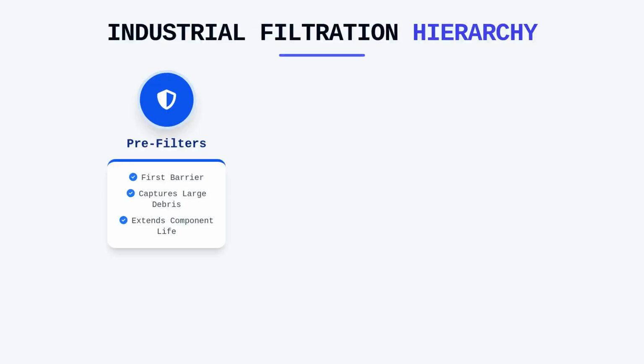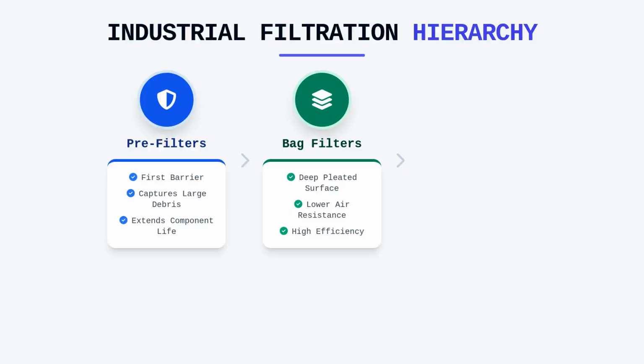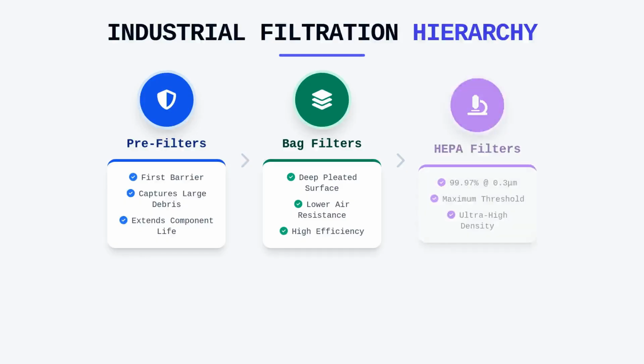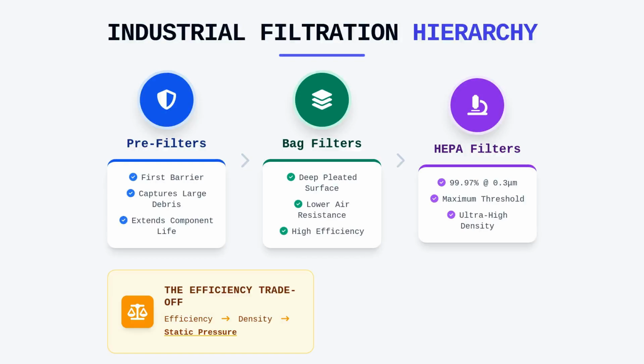Understanding these physical mechanisms is vital when comparing different types of media, such as standard pre-filters, multi-pocket bag filters, and high-efficiency particulate air, or HEPA filters. Pre-filters serve as the first barrier, designed to capture larger debris and extend the life of more expensive, higher-efficiency downstream components. Bag filters utilize a deep, pleated surface area to maintain high efficiency while offering lower resistance to airflow compared to some rigid alternatives. HEPA filtration operates at a much higher threshold, typically requiring 99.97% efficiency at 0.3 micrometers.